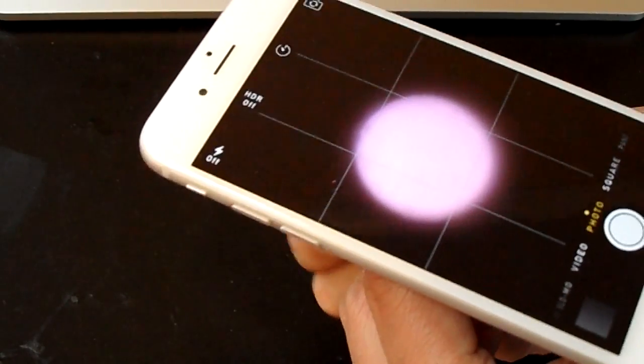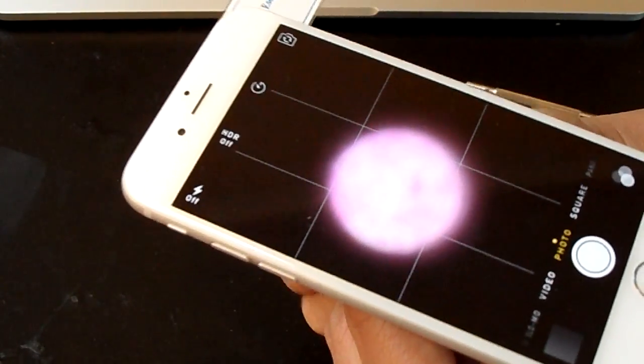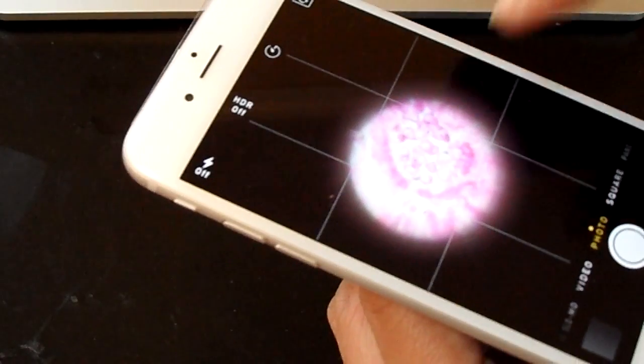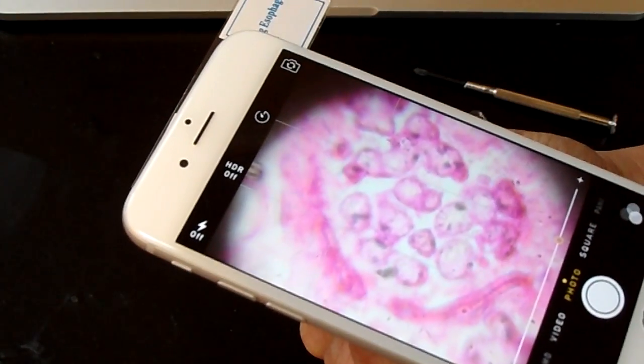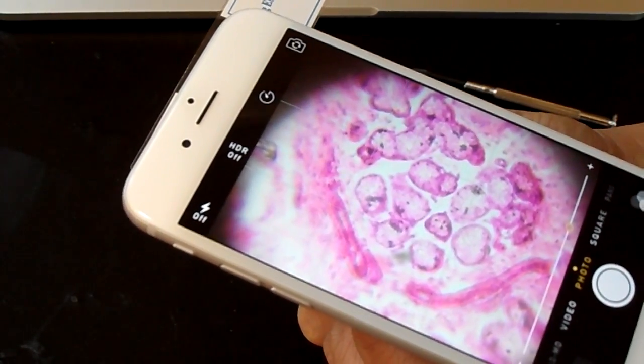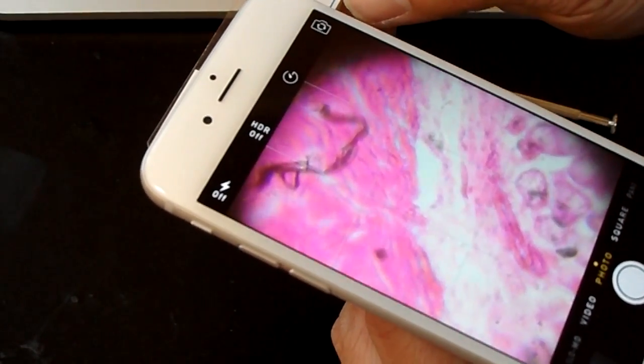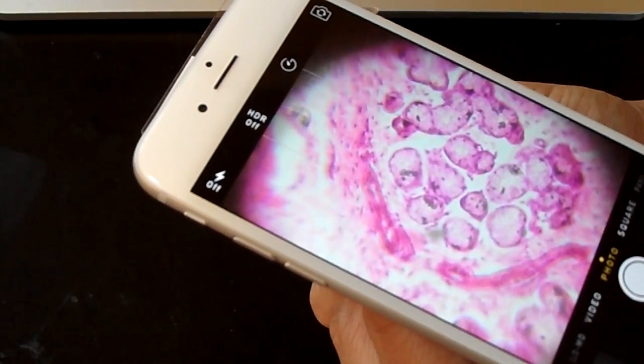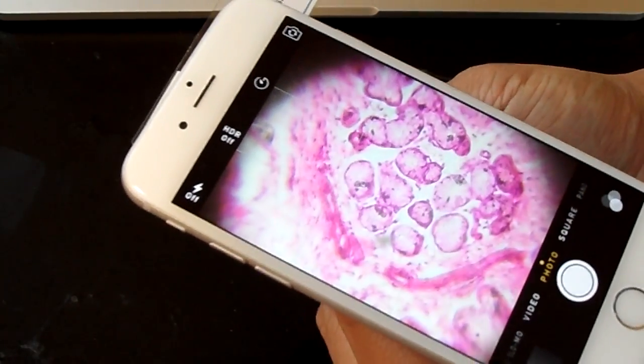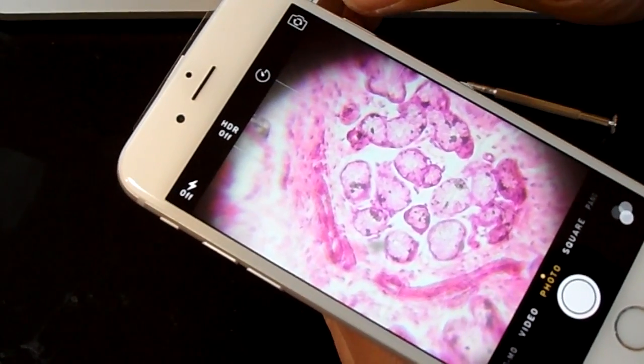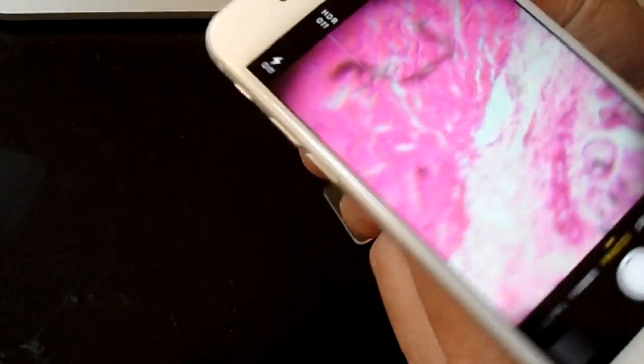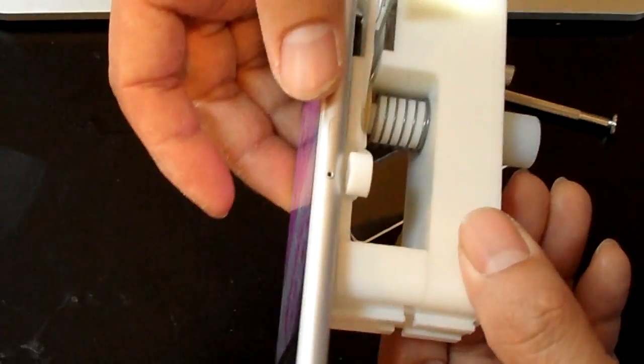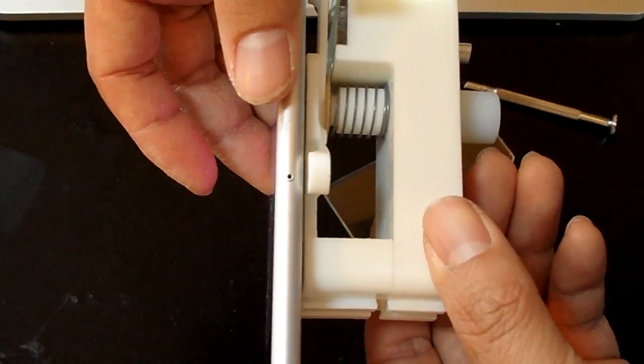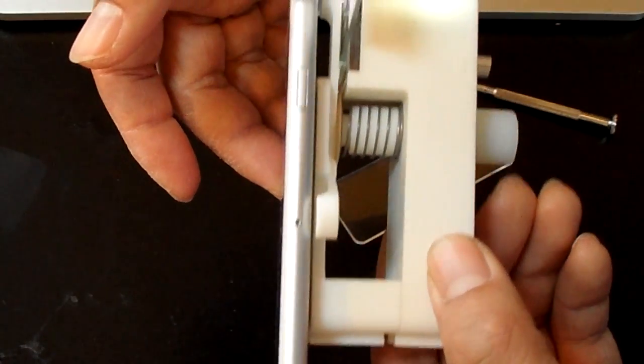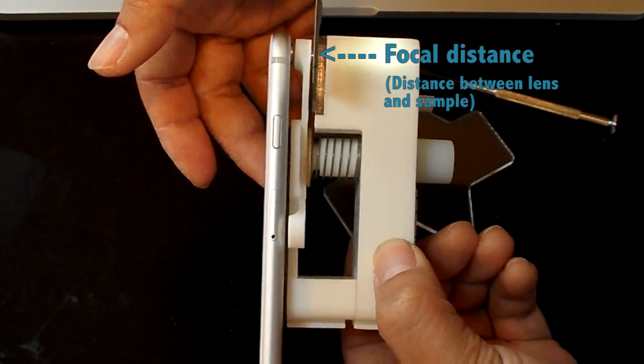So now I've switched it over to the 170x lens, and as you can see, this is how it looks as you're focusing the image. You won't really get very much until you get pretty much at the focal distance. And you want to make small adjustments and inch your way towards that perfect, focused image. Now the main thing I want to show you here is again, the proper distance to get a focused image. And really what you want to focus more on is the distance between the lens and whatever you're looking at. And as you can see, they're really close. They're almost touching each other.